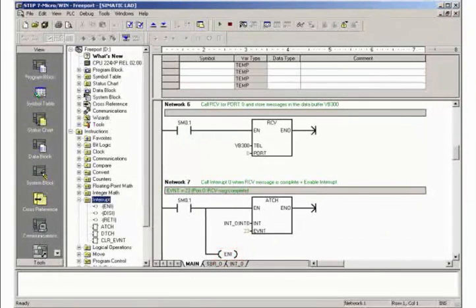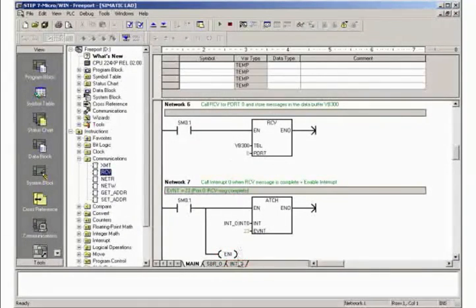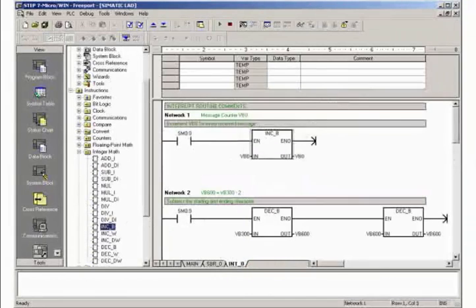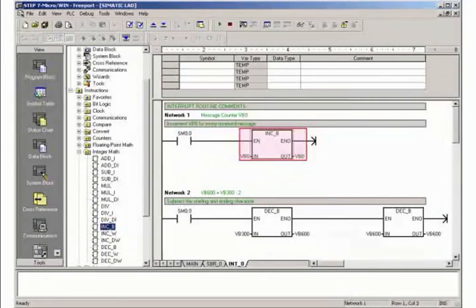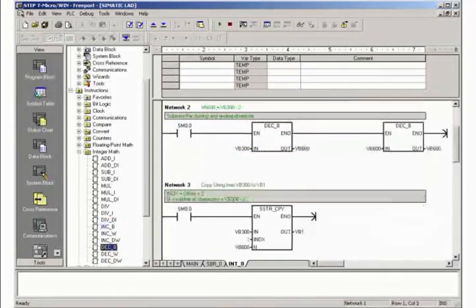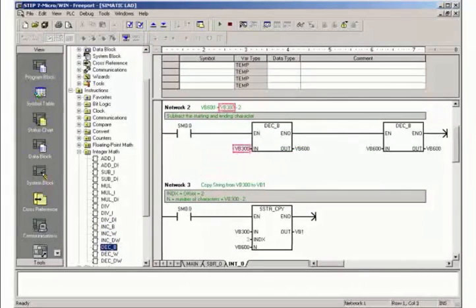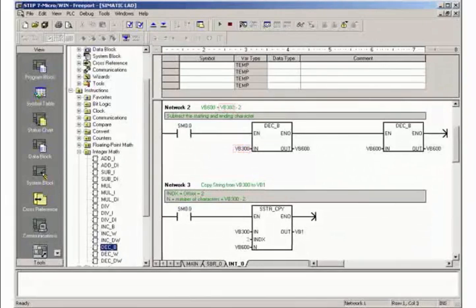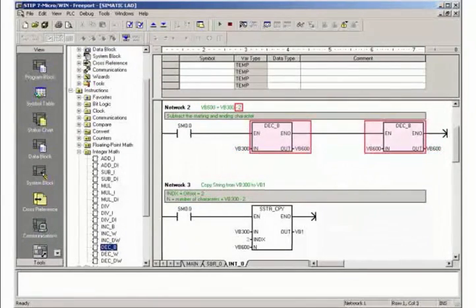Now go to the programming of the interrupt routine. In Network 1 of the interrupt routine you increment the message counter VB0. The number of received characters is stored in the start address byte of the data buffer. To determine the number of the user data characters, the start and end character are deduced from this.